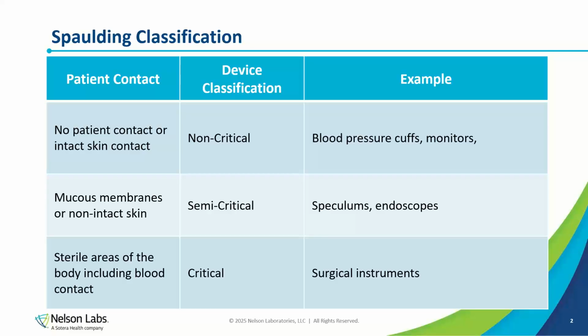Yeah, so high level disinfection, again, that's going to be for your semi-critical devices. And you are going to use a mycobacterium species to challenge the high level disinfection process. And you need to achieve a 6-log reduction with that mycobacterium species. Oftentimes, high level disinfections are performed using a high level disinfectant or chemical sterilant, and the device has to be fully immersed in that chemical disinfectant. So products like Cidex OPA or Sporox 2, these are common high-level disinfectants, and they require the device to be fully immersed. So if your device can't be fully immersed, then high-level disinfection is not going to be a possibility for that particular device.